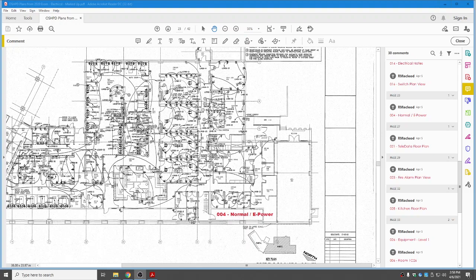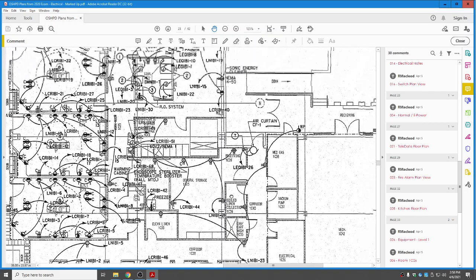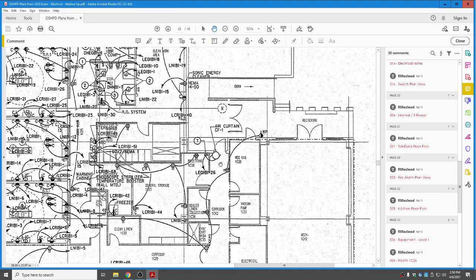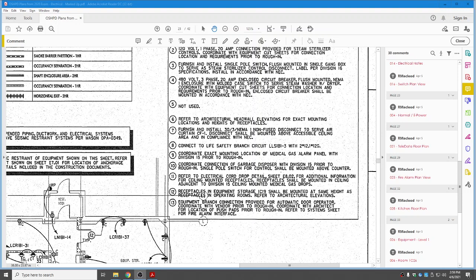Okay, let's take a look here at this air curtain, CF-1. Here's where it's located. It's on panel LEQ 1B1. That's the equipment branch, circuit 26. And we have a motor in there. And it's air curtain CF1. At that CF1 air curtain, there was a circle number 7 next to it that says furnish and install a non-fused disconnect to serve the air curtain CF-1. And the disconnect shall be mounted above accessible ceiling area and in compliance with the NEC.